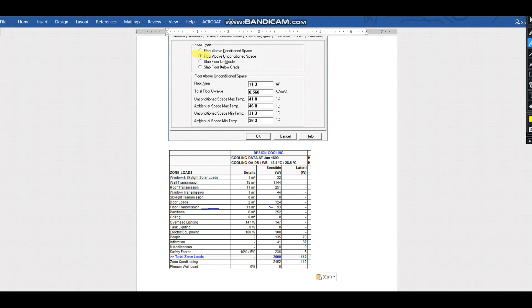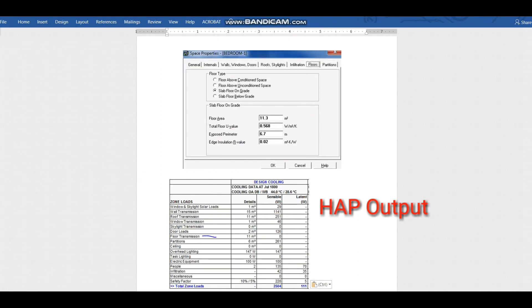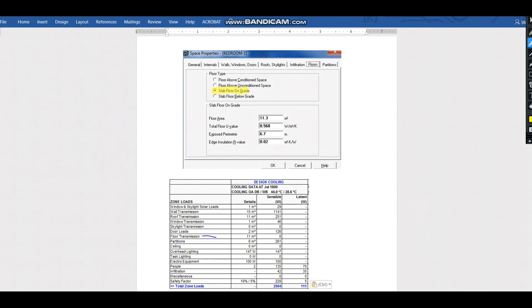For floor above unconditioned space, as shown in the HAP software, the floor transmission gives 93 watts of sensible load — that is the heat transferred when the below floor is unconditioned. If the floor is above conditioned space, there is no heat transfer since the floor below is also air-conditioned. For slab floor on grade with 11 m² floor area, the load is almost zero.